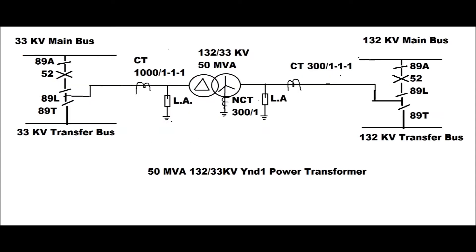The single line diagram for the 50 MVA 132/33 kV power transformer is shown in this figure. On the right side there exists the 132 kV main bus and transfer bus. On the left side there exists the 33 kV main bus and 33 kV transfer bus. 89A, 89L, and 89T are the main bus side, line side, and transfer bus side isolators respectively, for both 132 kV and 33 kV sites. The HV side CT ratio is 300/1 and the LV side CT ratio is 1000/1.